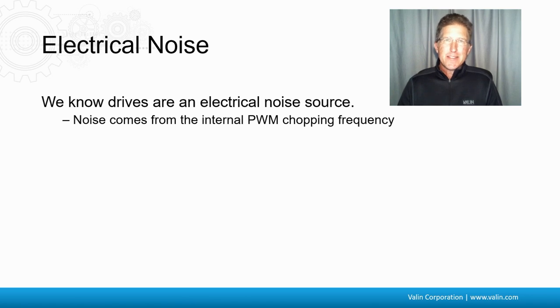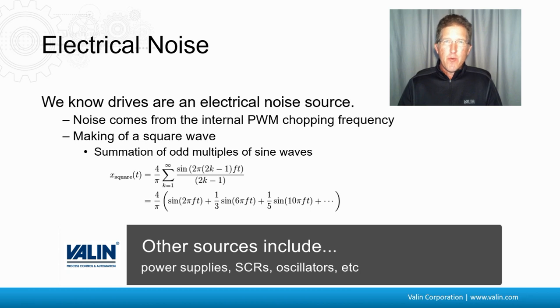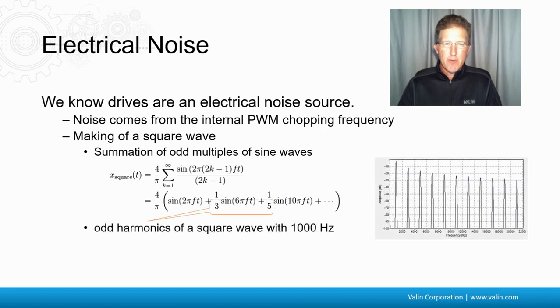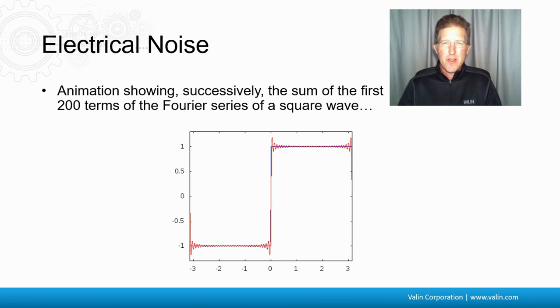Electrical noise is caused by some source. Servo drives, stepper drives, and VFDs are sources of electrical noise because they have PWM switching frequencies created inside of them. This is caused by the making of the square wave used to control the current to the motors. It has a summation of a bunch of odd multiple sine waves — the odd harmonics of the square wave. This animation shows the sum of the first 200 terms of the Fourier series of a square wave.